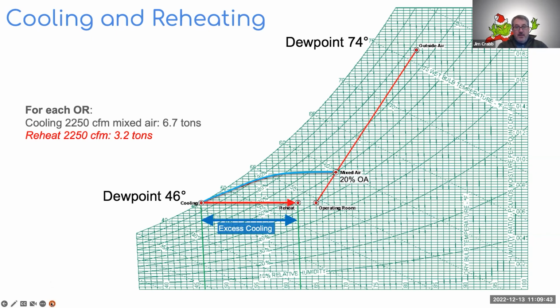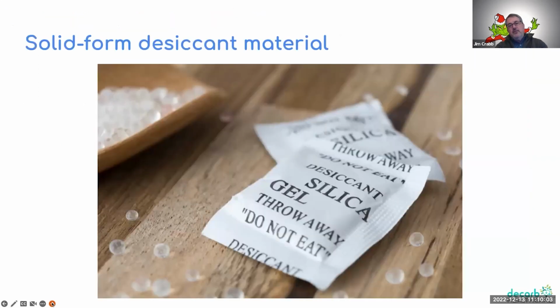And then we have to reheat it, because if we deliver 20 air changes of 46 degree air to an OR, it's going to get cold, too cold, and it'll still be high humidity. So we raise the temperature back up, and that's one example of where reheat is used all the time, 24/7 in most ORs. For typical spaces, it's not quite that dramatic, but ORs are a good example.